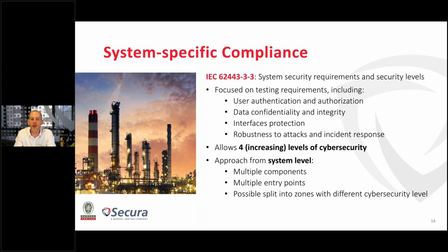On top of that, it requires that the control system is under configuration control and under version management. And this is sort of a disclaimer by IEC to say that if your system is not using configuration control and version management, you won't be able to achieve certification anyway, so don't spend energy on pursuing it at the moment. Something interesting is also that there is no requirements about sizing or scalability. So both fixed size and scalable deployments can be certified under a 3-3 scope.